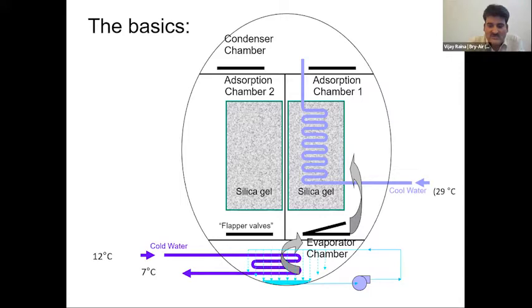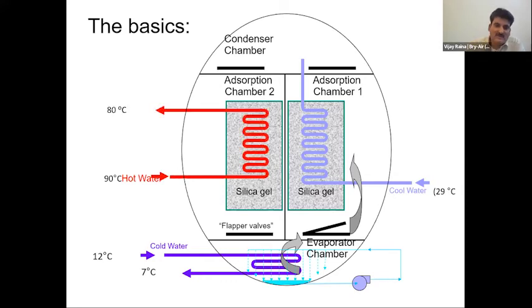So no electricity is consumed in this chiller. It's a natural refrigerant moving from the evaporation chamber to the silica gel chamber 1. And we are giving 2 utilities: one, cooling tower water to keep the chamber cold so that proper adsorption happens in chamber 1. At the same time, we are giving heat. Now, hot water plays a very important role in this. When we get hot water at 90 degrees, or 70, 60, the minimum limit is 60, the maximum is 90, 95, we can use it in this technology as hot water.